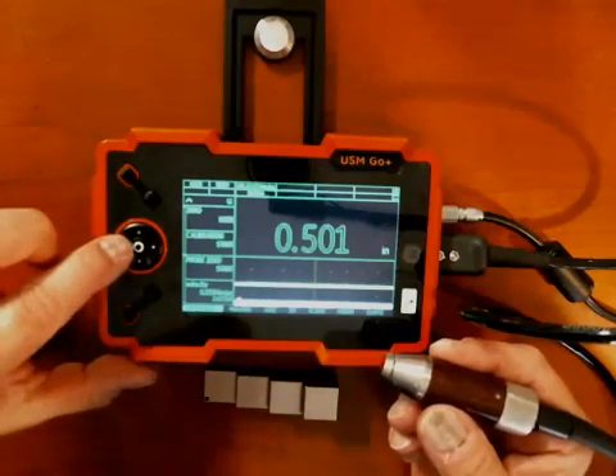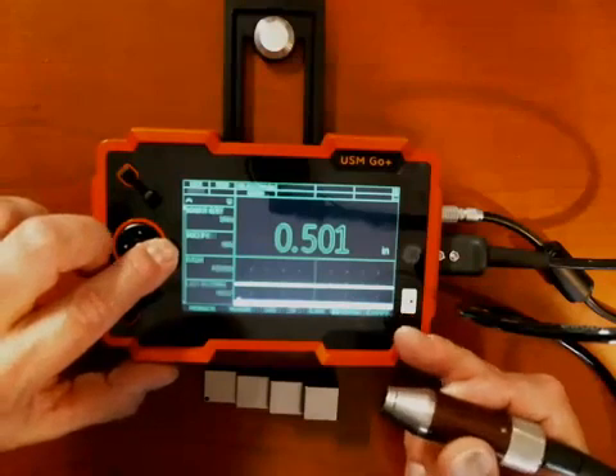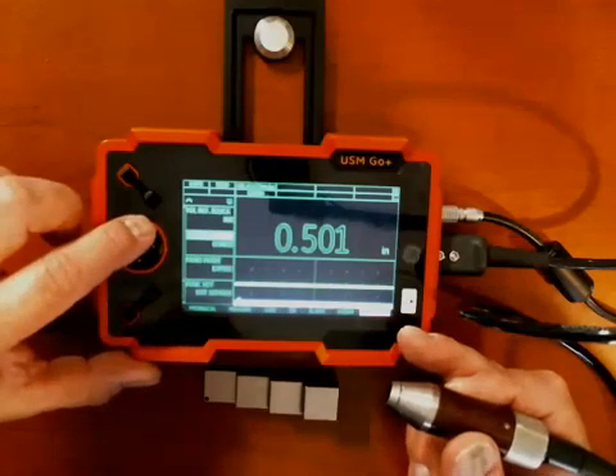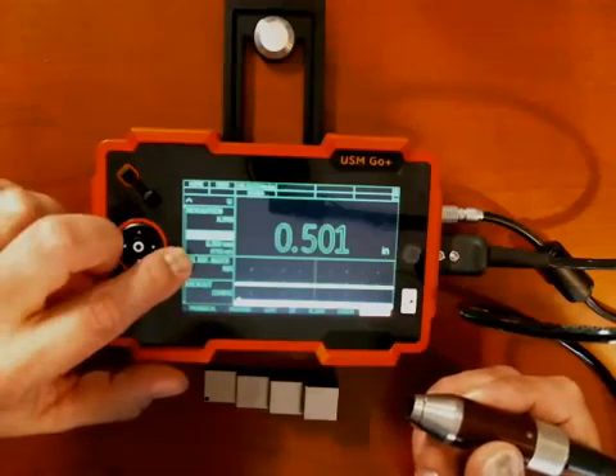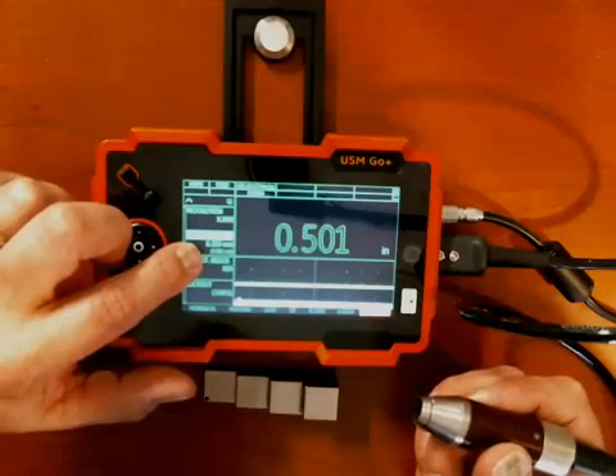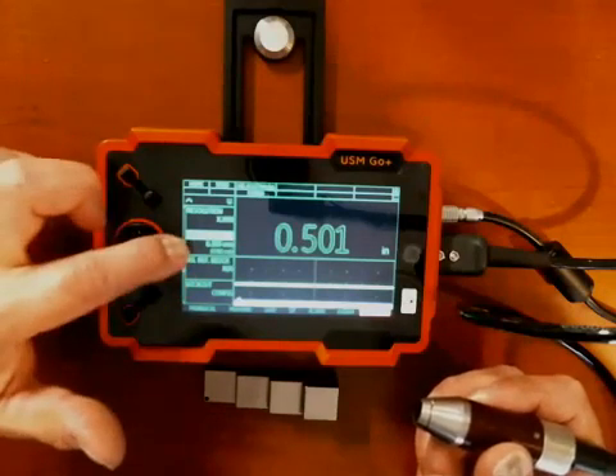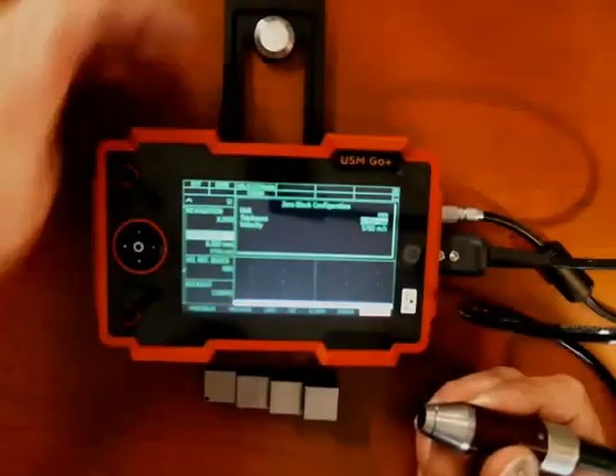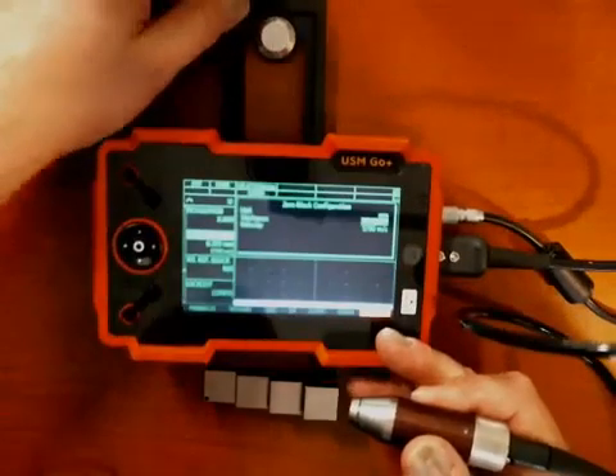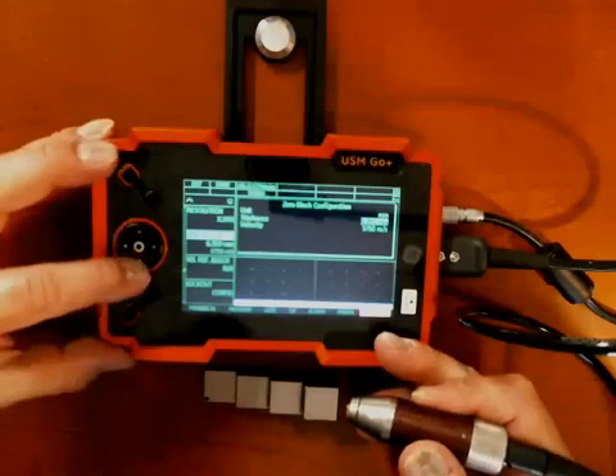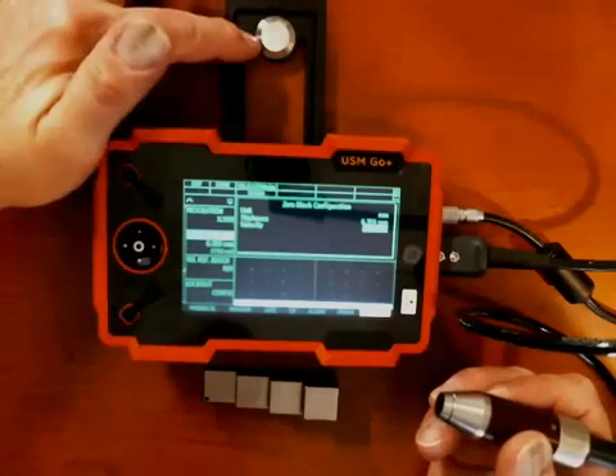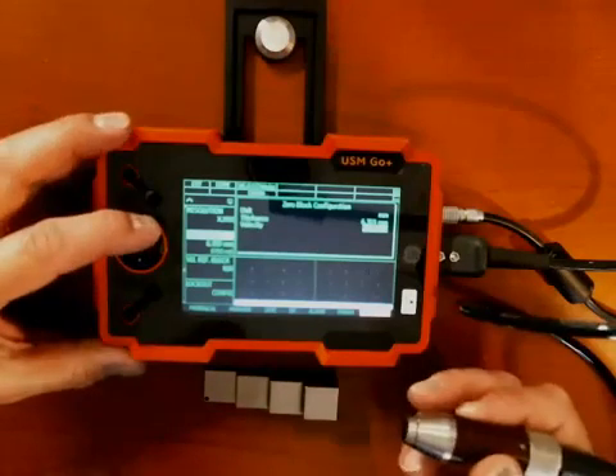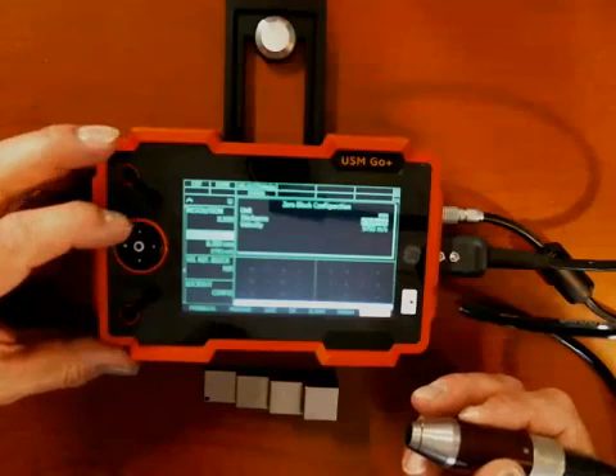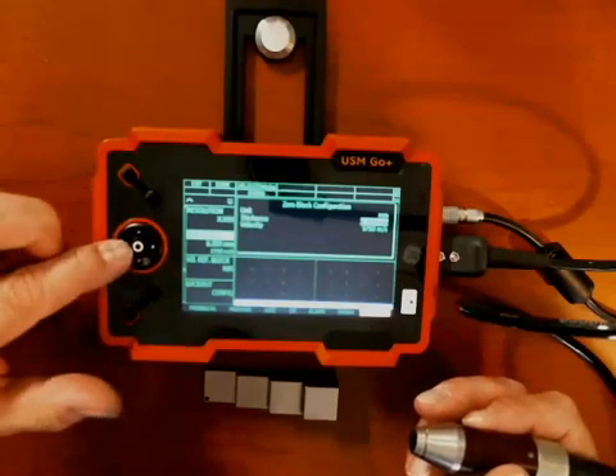So normally we'd start out in the probe and cal menu. If I go over here to the config menu and go up to the zero block parameter, there's two numbers shown, a thickness and a velocity. If I come onto that parameter, I do the right arrow. It brings up a window where I can set those two numbers. On my block, I've already done this. My thickness is 6.359 millimeters. My velocity is 5950 meters per second. That matches the numbers on the block. If those numbers don't match, you can adjust them. Use the up and down arrows to select which of the two parameters, right and left arrows to increment and decrement the numbers. Again, make sure that those numbers match.